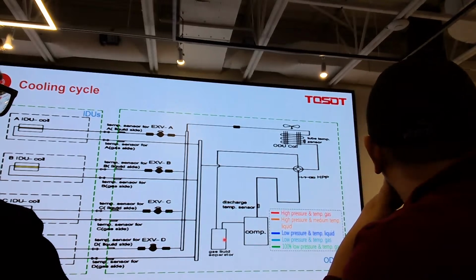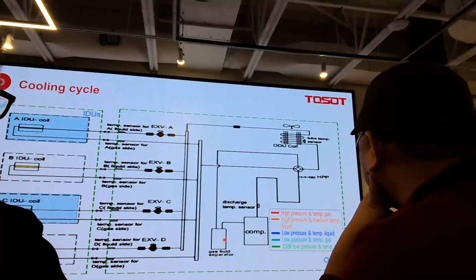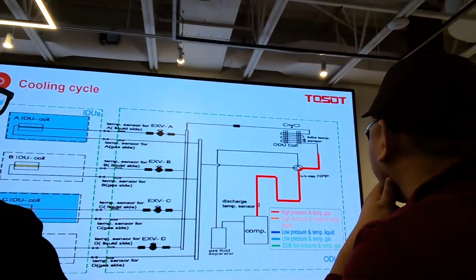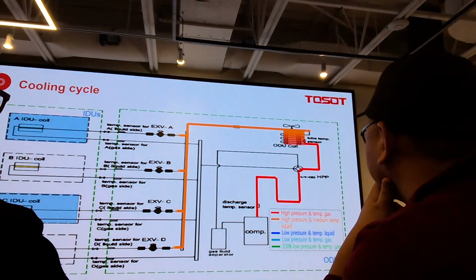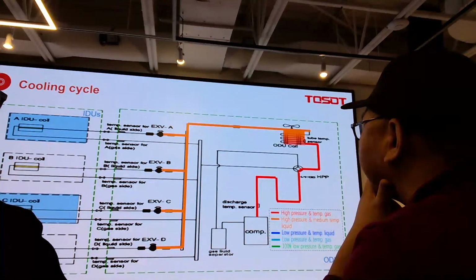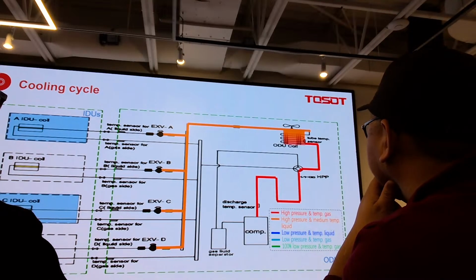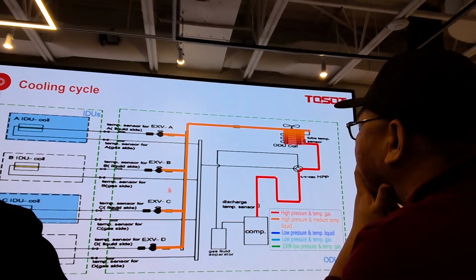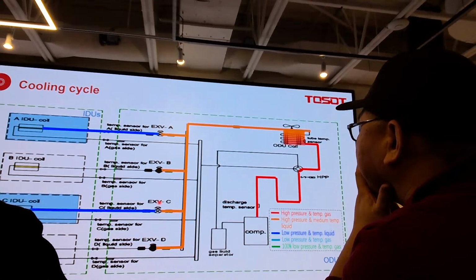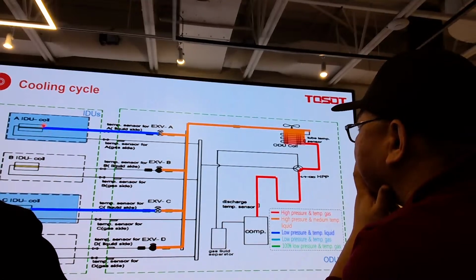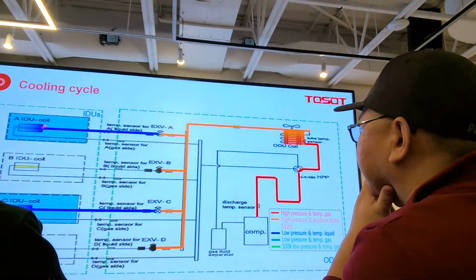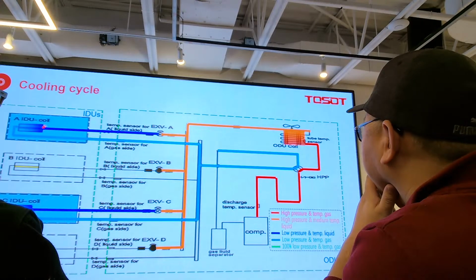So to make it simple, how does the refrigerant flow in cooling mode from the compressor? Let's say these 2 indoor units require cooling. The refrigerant from the compressor will first go to the outdoor unit and release heat, and then it will become liquid. This time only A and C require cooling, so the A and C EXVs will do the metering, and then offer this cold refrigerant to the indoor side to absorb heat. Then it becomes gas and flows back to the outdoor unit, just like this.